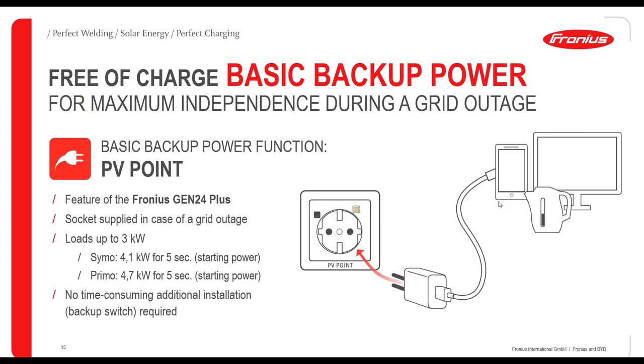And this socket, the so-called PV Point, is supplied in case of grid outage with the PV yield which is currently generated. That means in a daytime situation, you can take out energy from this socket and supply loads up to 3 kilowatts. That means you do not have to pay extra fees or have extra costs. This is standardized, integrated in our devices, and you also do not need a backup switch or additional installations. So this is automatically handled by the inverter. You just have to configure it during initial commissioning.